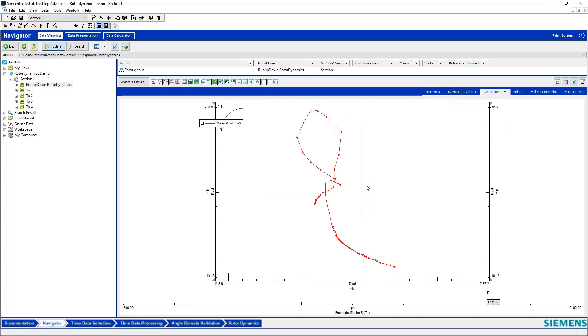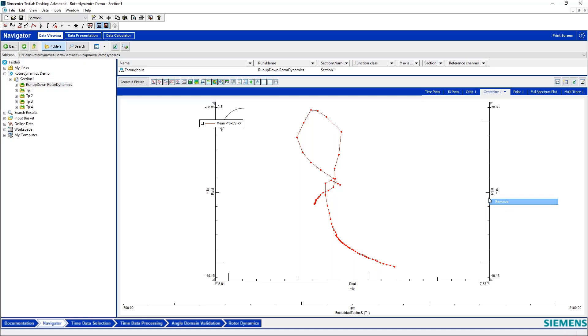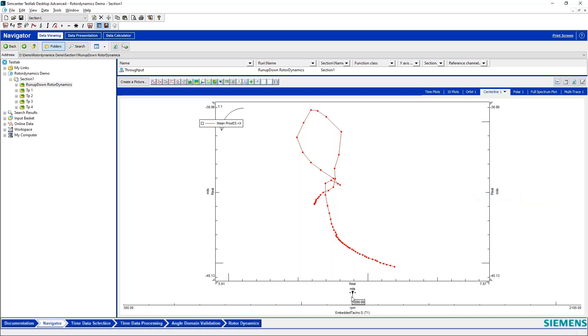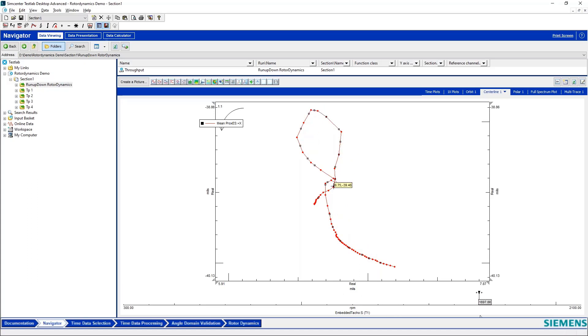I have a shaft centerline plot here so I can see, I'll add a cursor here to my rotational speed axis, and then if I highlight my curve I can see, all right at 300 RPM this was the location of my shaft centerline, and then as I sped up the machine I can see how and where my shaft centerline moved.